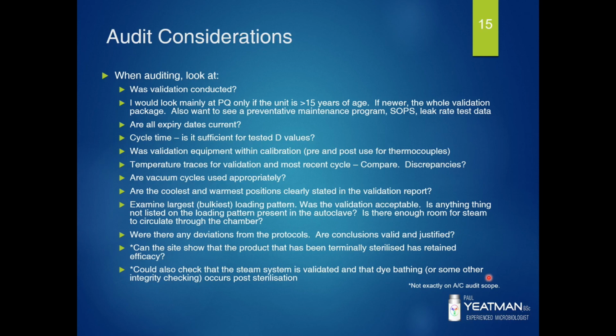So as part of your auditing, you'd want to look at the autoclave, say after a cycle has been completed, and with reference to the loading pattern, once the autoclave has been opened up, determine if anything is in the autoclave that's not in the loading pattern. If that is the case, then clearly the procedures aren't being followed, and that's a big red X, and that's something that needs to be addressed.